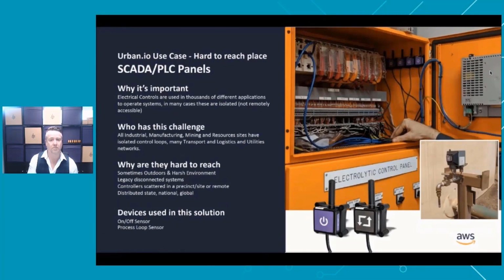Disparate SCADA PLC panels - we see literally thousands and thousands of disconnected, isolated PLC loops. This is a bit more sophisticated one, and you can see a bunch of our sensors wired into this cabinet. We're literally wiring into the SCADA panel and piggybacking off the readings running through the SCADA - so we're either reading a dry contact relay saying am I on or off, triggered or not triggered, normally open or normally closed, or we have a 4 to 20 milliamp sensor that can read a 4 to 20 milliamp output.